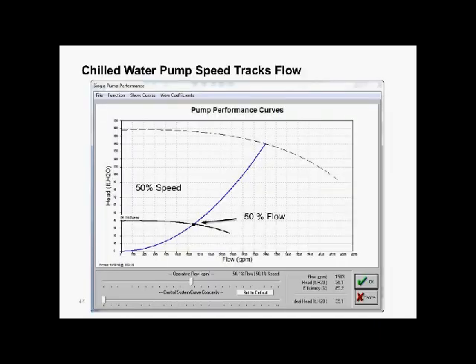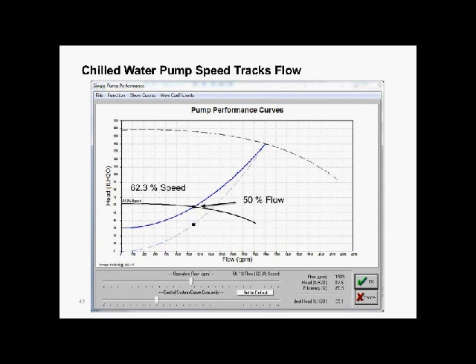Okay, let's take a look. This is a head capacity curve up here, and this is our ideal system curve to 0. You'll see that as I reduce speed down to 50% right here, as I reduce flow, I'm at 50% flow and my speed is at 50%. So when you have an ideal system curve going to 0, the affinity laws apply, and speed tracks flow. But that's not what happens in chilled water systems.